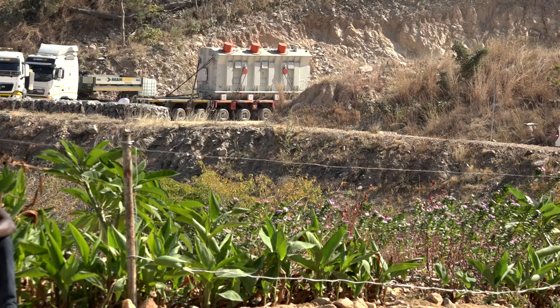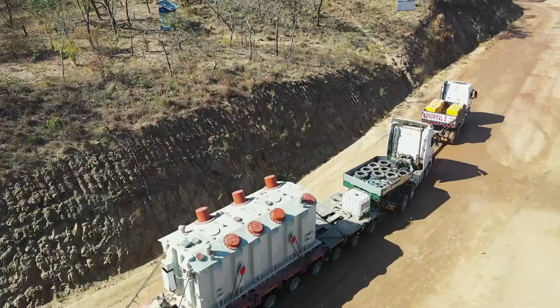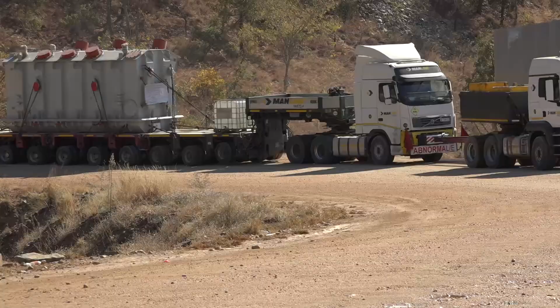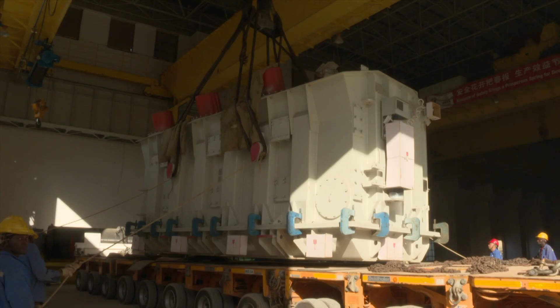Kafue Gorge Lower Hydropower Project will have 5 generating units, each rated 150 megawatts. Each of the generators will be connected to a generator transformer, and these generator transformers have started arriving. We'll be generating at 13.8 kilovolts, and we need to transmit this power to the national grid at a higher voltage, so for us to be able to do that, this is key, the transformers.